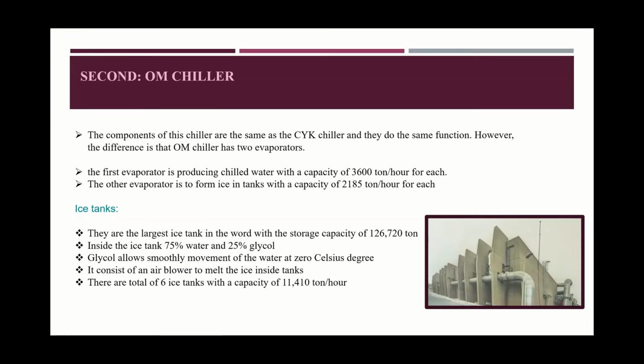When it comes to the OM chiller, components of this chiller are the same as the CYK chiller and they do the same function. However, the difference is that OM chiller has two evaporators. The first evaporator produces chilled water, while the other is responsible for producing ice. The first evaporator is producing chilled water with the capacity of 3,600 tons per hour for each. The other evaporator is to form ice in tanks with the capacity of 2,185 tons per hour for each.